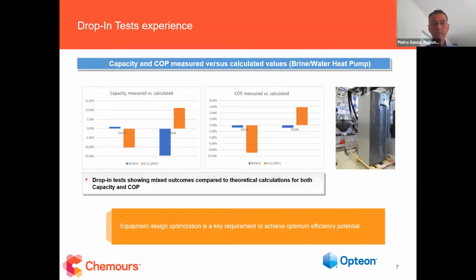The graph shows relevant gaps between expected performance—projected and theoretically calculated—and the tested outcome in a number of scenarios. Other parameters intersect this problem too. One is the growing intelligence on board of modern heat pumps; in some cases they have learning capabilities, and the adaptation of the refrigerant passes through algorithms that the controller imposes on the machine. Unless the components, system, and software are designed for the specific thermodynamic properties of the refrigerant, it's difficult to achieve the best that can be achieved with that refrigerant.